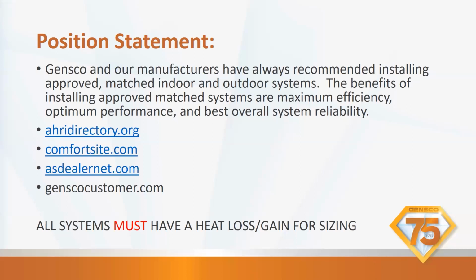All systems must have a heat loss and heat gain for sizing. No exceptions. If you're not doing that, you don't know what size the house needs for you to put in the correct equipment. I know a lot of people try to match off of current equipment, but if the original guy didn't do his job and we don't know whether they did or not, you're going to have issues with airflow, noise issues, overall system capability. You need to know what you need for the house before you can install it. So do a heat loss and heat gain on every job.